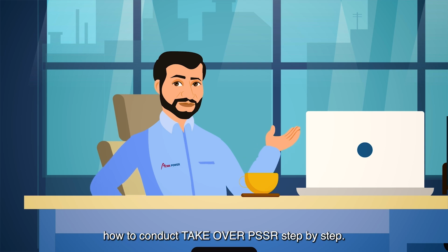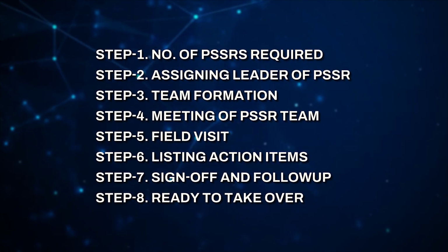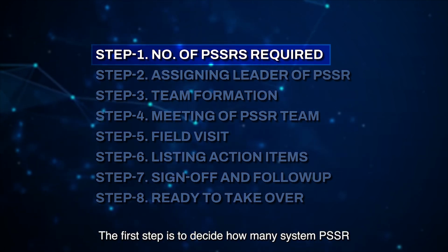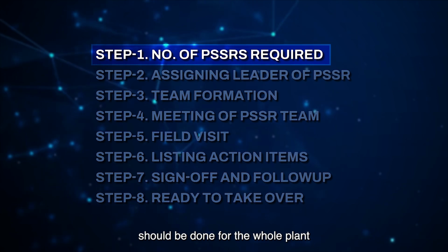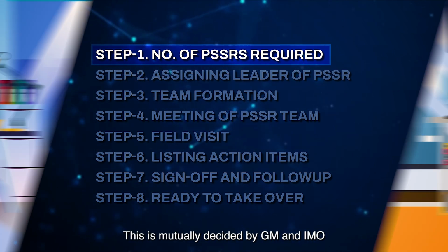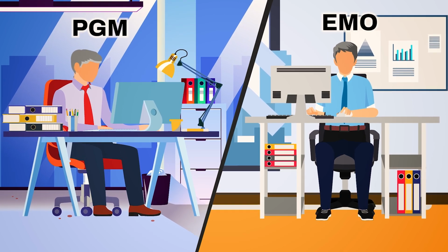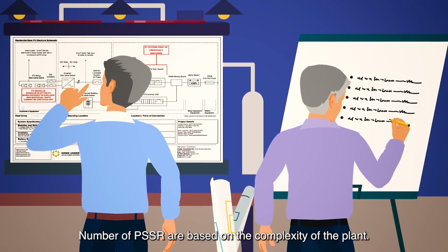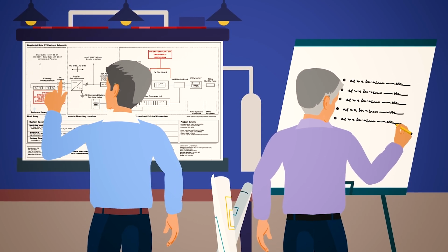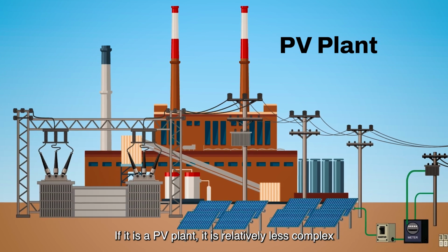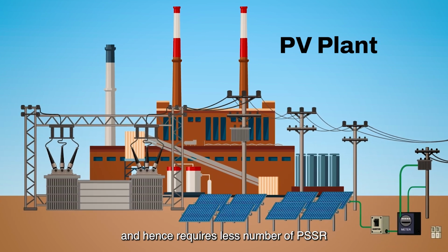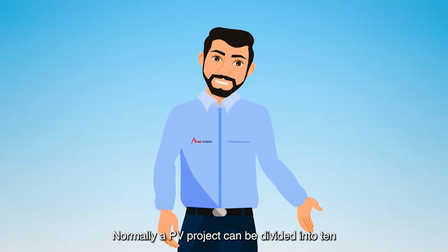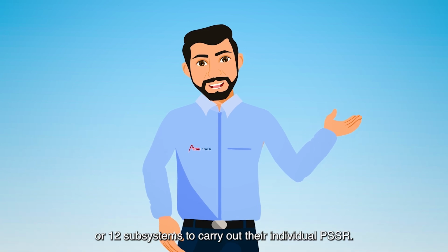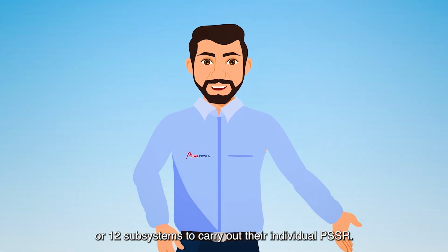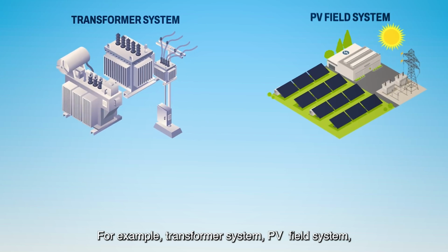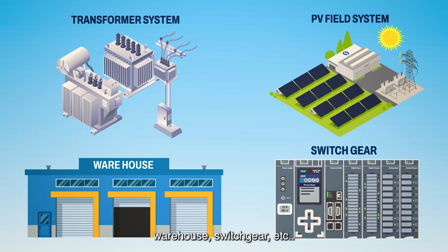Now let's learn how to conduct Takeover PSSR, step by step. The first step is to decide how many system PSSRs should be done for the whole plant which is being taken over. This is mutually decided by PGM and EMO. The number of PSSRs is based on the complexity of the plant. If it is a PV plant, it is relatively less complex and hence requires fewer PSSRs. Normally, a PV project can be divided into 10 or 12 subsystems to carry out their individual PSSR. For example, transformer system, PV field system, warehouse, switchgear, etc.